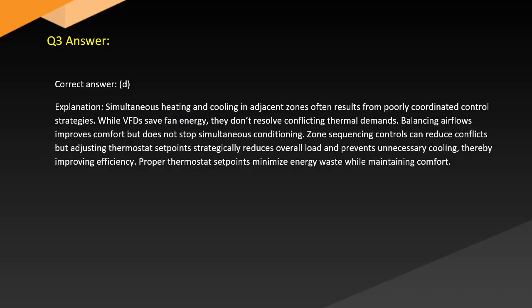Answer. Correct answer: D. Explanation. Simultaneous heating and cooling in adjacent zones often results from poorly coordinated control strategies. While VFDs save fan energy, they don't resolve conflicting thermal demands. Balancing airflows improves comfort but does not stop simultaneous conditioning. Zone sequencing controls can reduce conflicts, but adjusting thermostat set points strategically reduces overall load and prevents unnecessary cooling, thereby improving efficiency. Proper thermostat set points minimize energy waste while maintaining comfort.